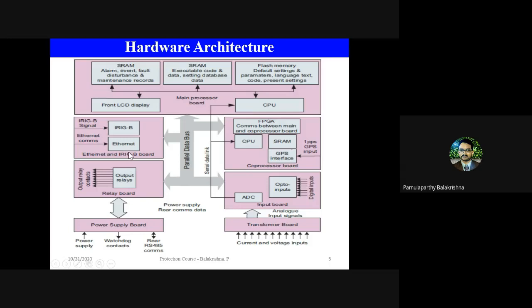Okay, so we have covered most of the components, and the last thing is the time synchronization input. As you might have heard and studied, either in WAMS or in synchrophasors, time is very, very critical in a power system, and all the devices in the substation are expected to be time synchronized with respect to a satellite time reference. For that purpose, either the relay can take the GPS input as an interface, or it can also take IRIG-B input. IRIG-B is nothing but Inter-Range Instrumentation Group. This is a standard, and they define how the time signal has to be transferred from the source to the receiver, and then from receiver to another receiver.